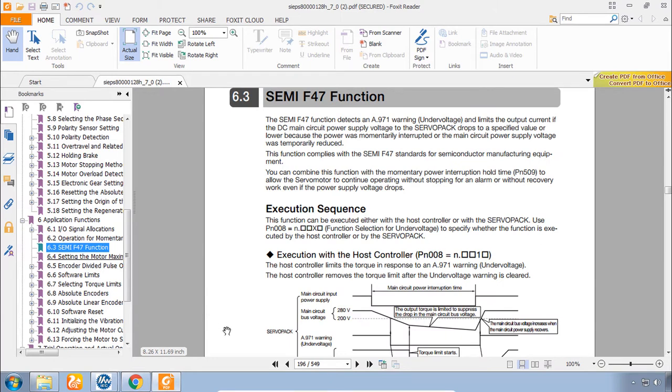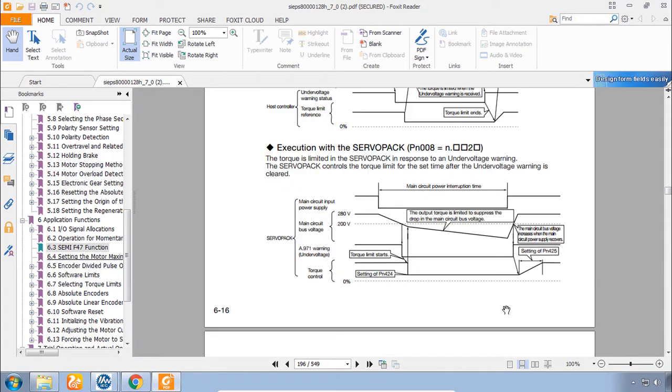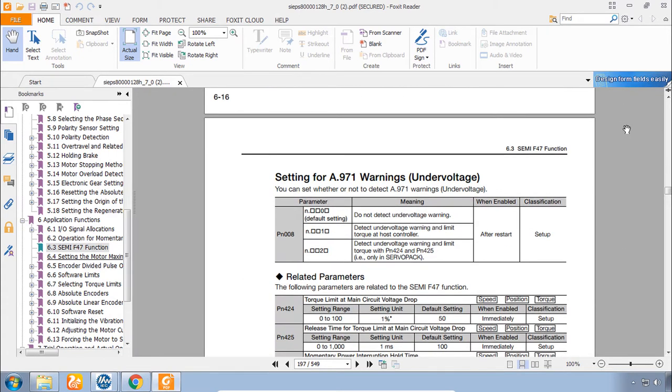Related to power outage is the Semi-F47. Semi-F47 is about power brownouts. Or voltage drop. You can get the amplifier to limit torque when there's an under voltage condition. Basically ways to keep the servo from turning off or throwing an alarm when there's a problem with the power input.